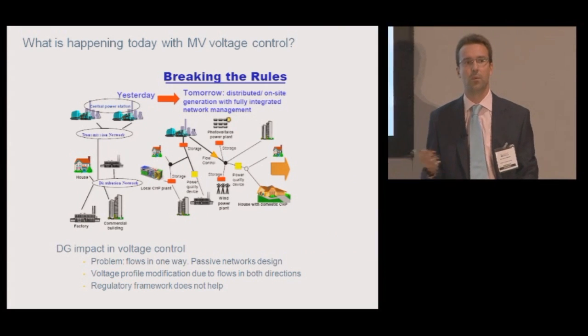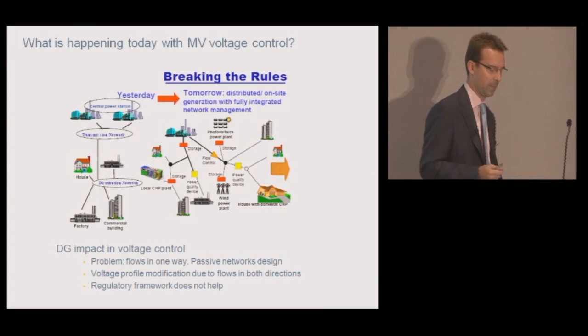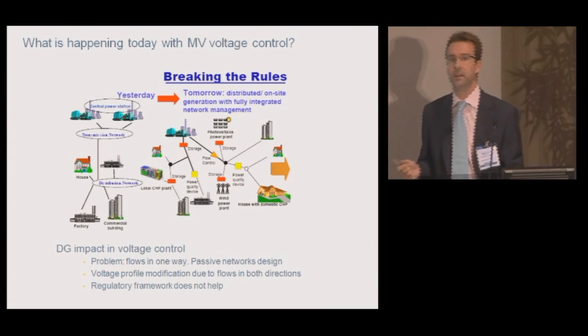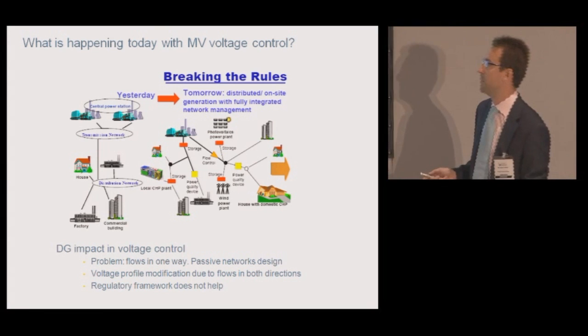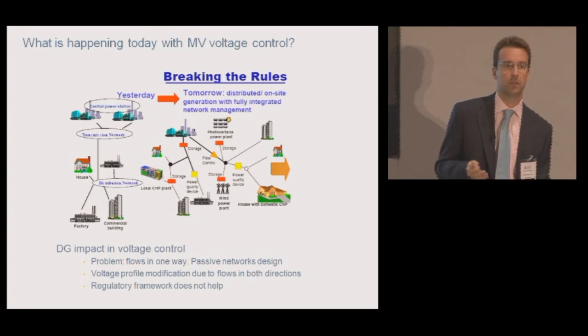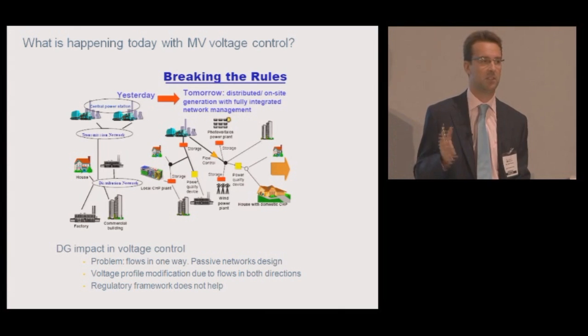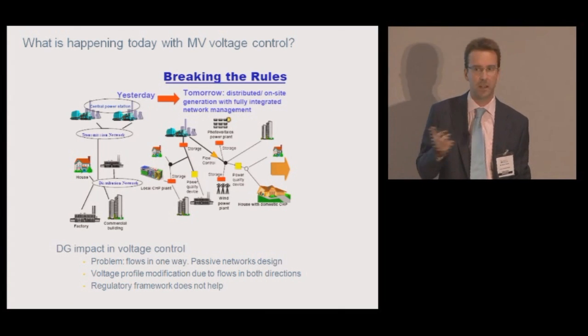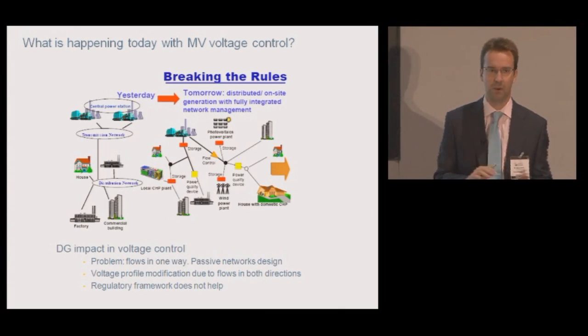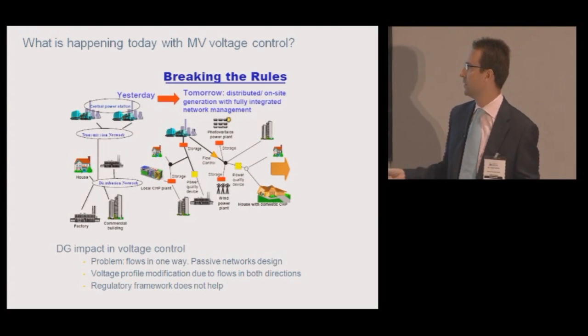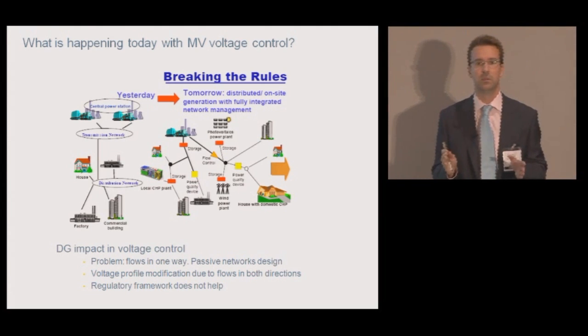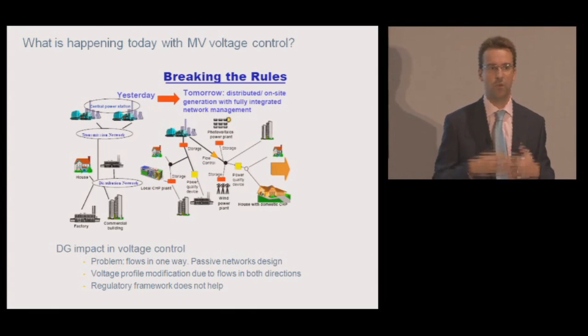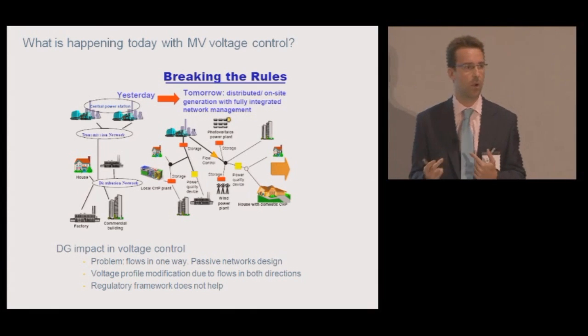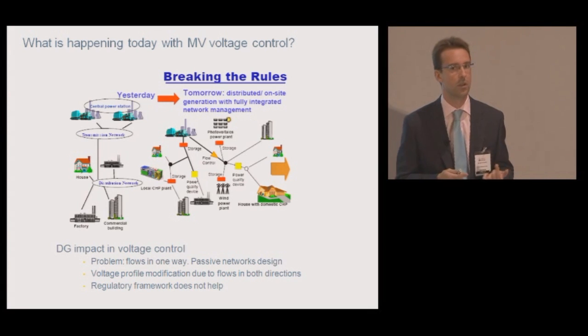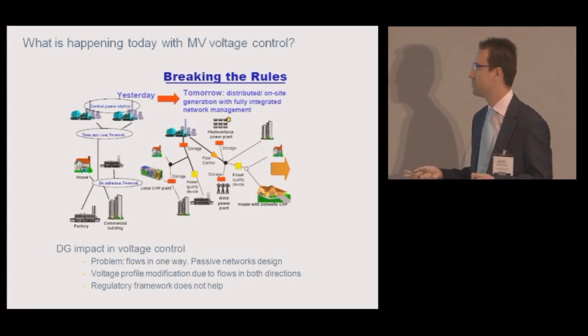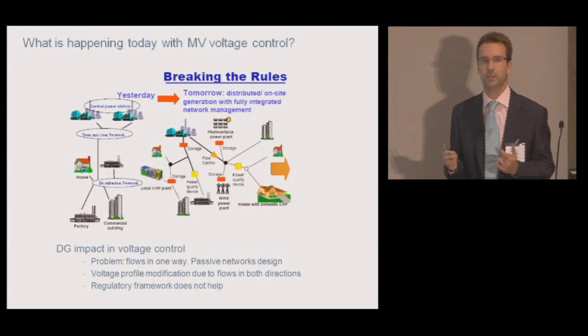What is happening when we talk about voltage control? Finally, we are breaking the rules. Why? Because all distribution grids have been designed in a passive way—meaning a very low monitoring level, with flows that are very predictable and only one-way. When distributed generation is connected, flows are no longer one-way, they go both ways. This affects the voltage profile the grid was designed for.